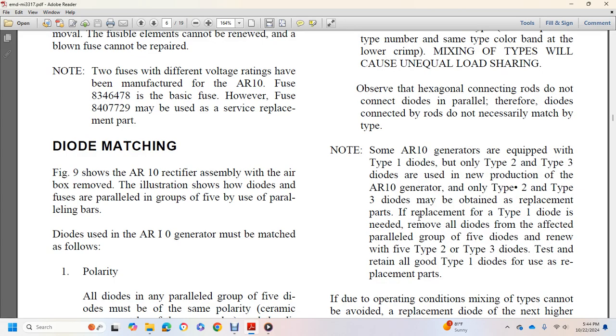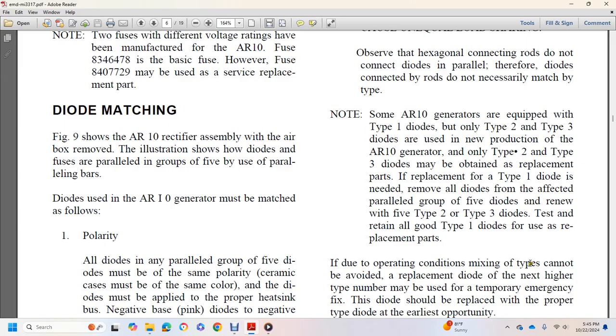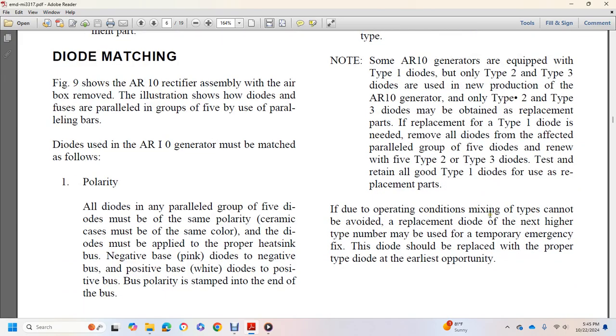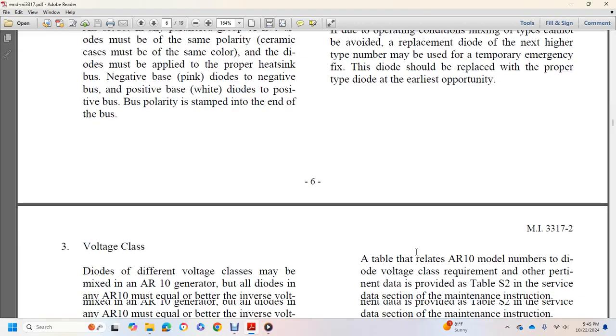If replacement of a type 1 diode is needed, remove all the diodes of the affected parallel group of five diodes and renew with five type 2 or type 3 diodes. Test and retain all good type 1 diodes for use as replacement parts. If due to operating conditions mixing of types cannot be avoided, replacing the diode with the next higher type number may be used as a temporary and emergency fix. The diode should be replaced with the proper type of diode at the earliest opportunity.